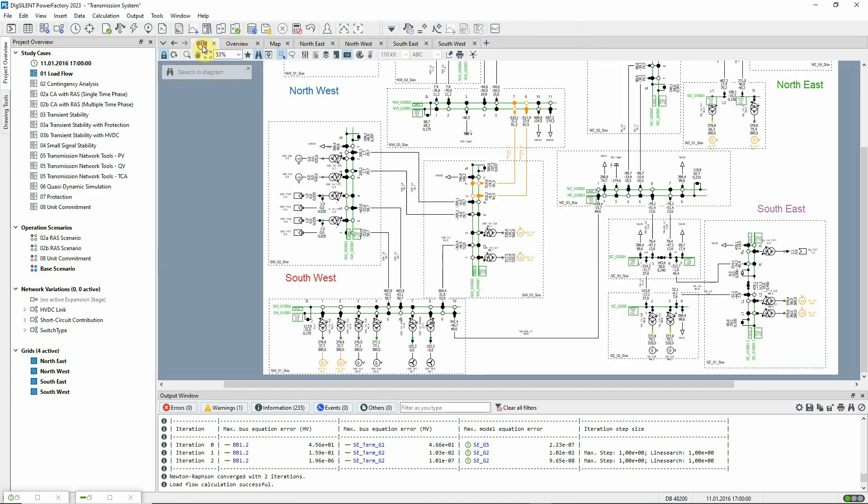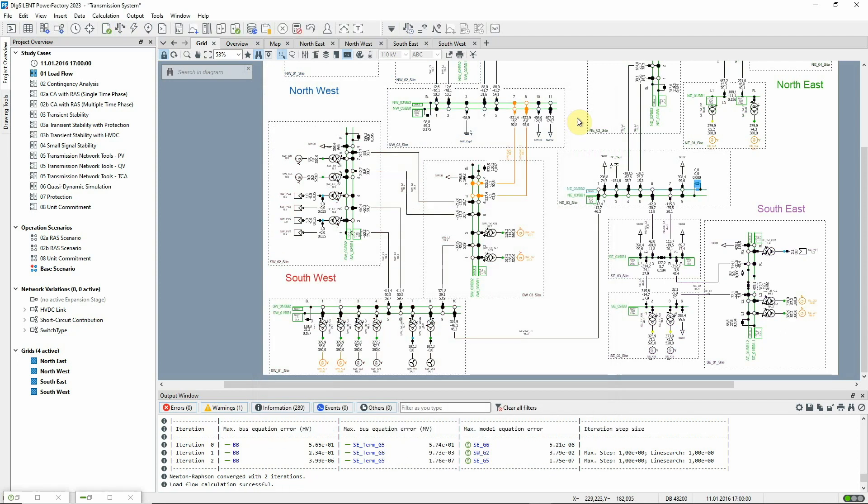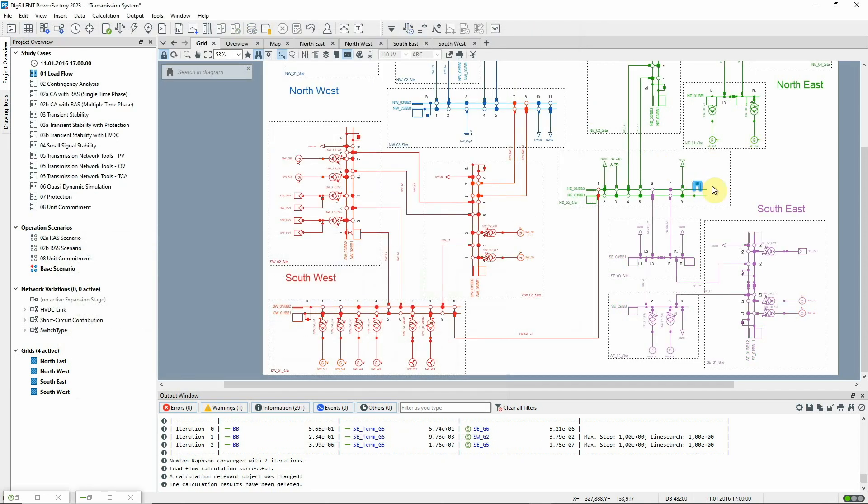We can split the substation from the grid graphic by double-clicking on the bus coupler to open it. We rerun the load flow. And we can see how the voltages are now quite different on the two sides of the split. The breaker is closed again.